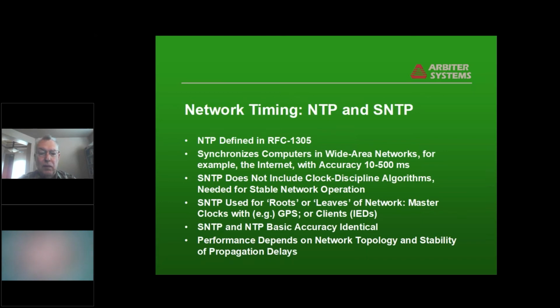This is used primarily for synchronizing computers and wide area networks, and the accuracy ranges in tens to even hundreds of milliseconds. The reason for that accuracy is that the longer the transmission path and the more uncertainty, the harder it is for the system to compensate for it. It does measure round trip delay, but as you know, with the internet, every packet goes by a different route. So there's a very good possibility that the packets used to measure the path delay will give a different answer than the packets that are broadcasting the time.